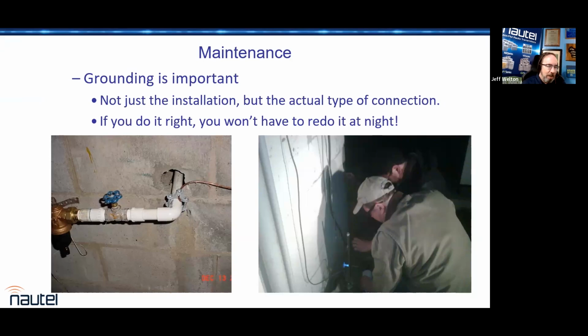Don't like them. So compression connections, everybody's heard this, but if you put a stranded copper wire in a compression connection, unless you displace all of the air, that copper will deform, because copper's malleable, and it will deform to displace air, and it'll become loose.